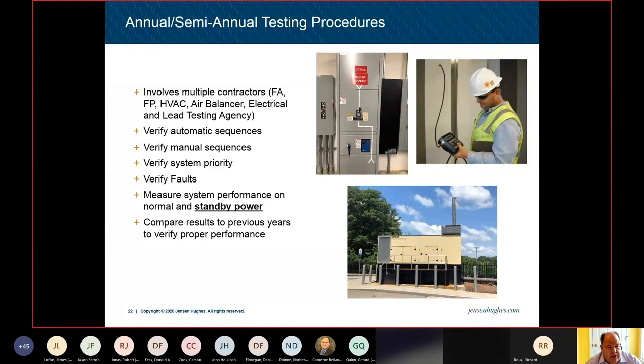But those manual sequences are very important to make sure of, because we check the priority. They're supposed to have a number one priority over everything else. We verify system priorities. You don't want the HVAC system freeze stats, which turn off the fans if it's too cold outside, turning off in the middle of a smoke control system.